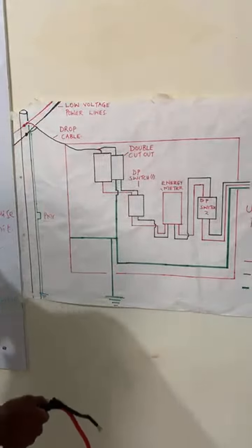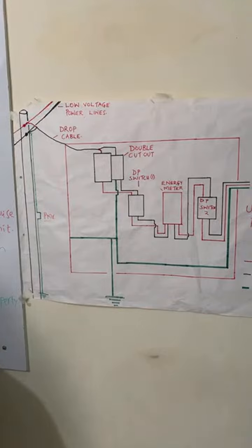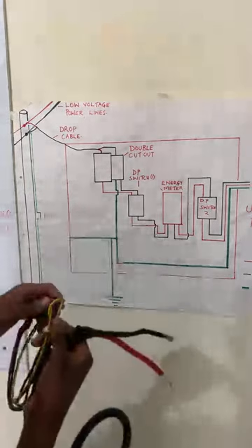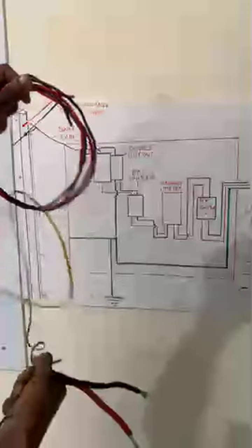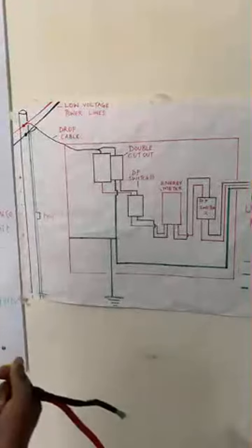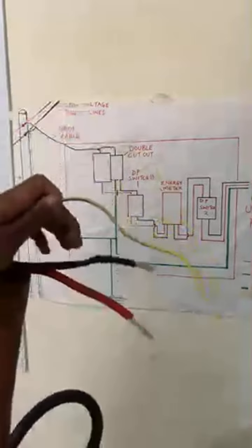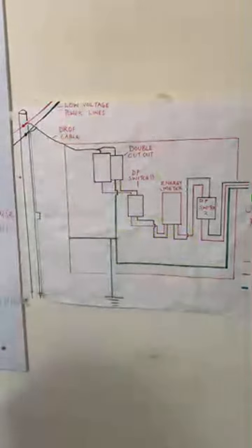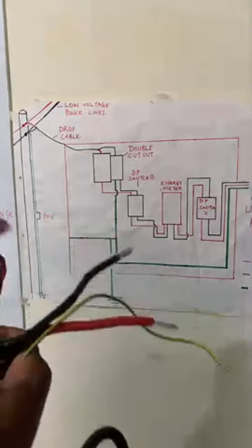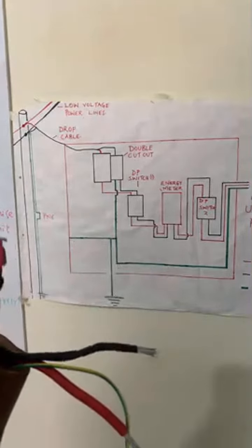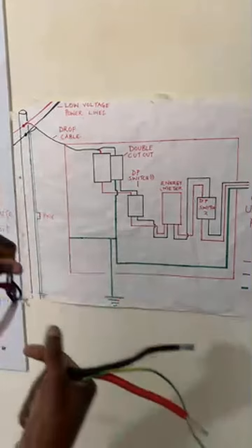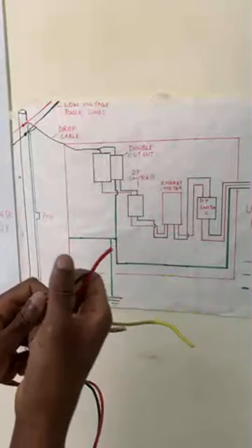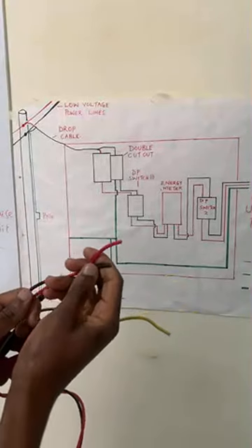So how do you obtain that connection? Let me just demonstrate it to you right now. If we have the earth connection here, this is our earth connection, this yellow with green. So if you're just a beginner electrical technician, you really get used to this connection. And so you must familiarize yourself with the color codes. Again, remember, it also depends on your country. What color codes are you using for the phase? What color code are you using for the neutral or the return? And for the earthing connection, I know it is usually standard worldwide, if I'm not wrong.